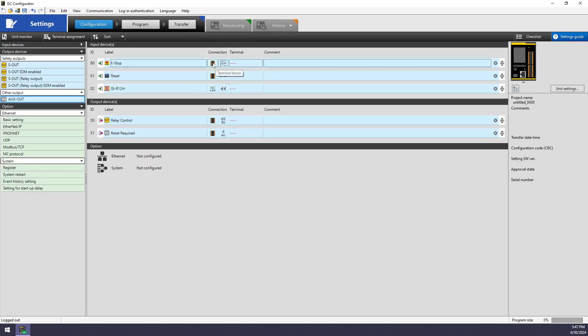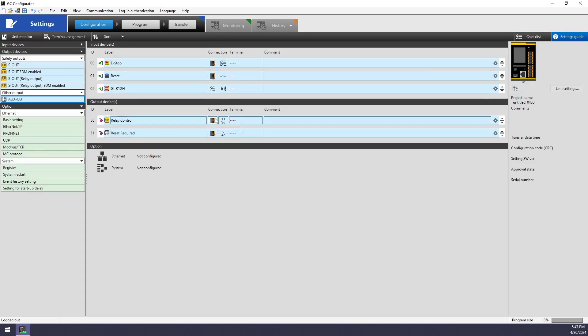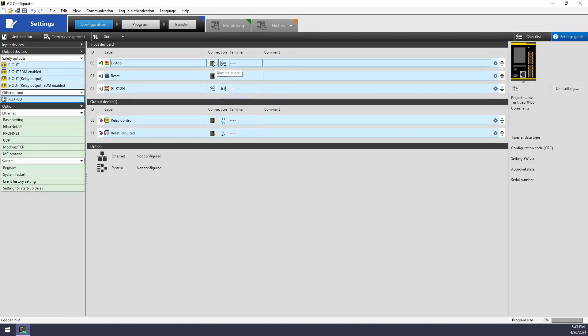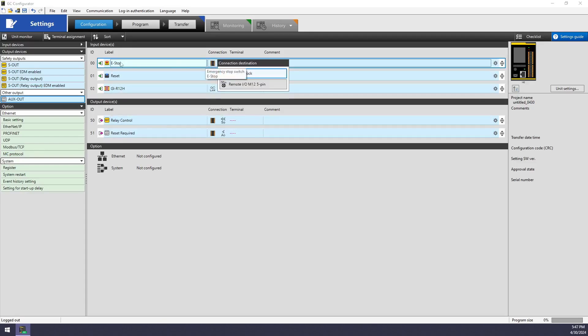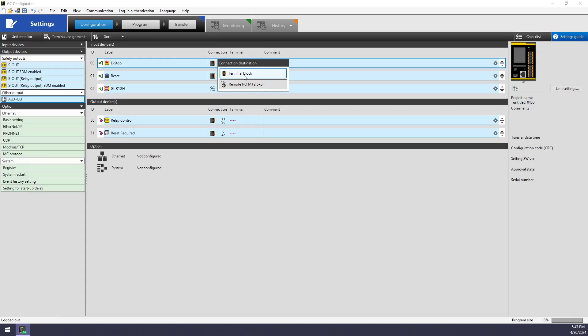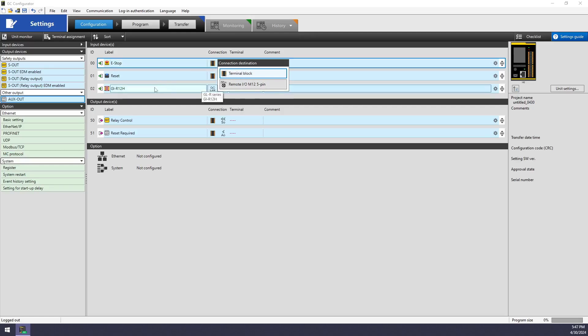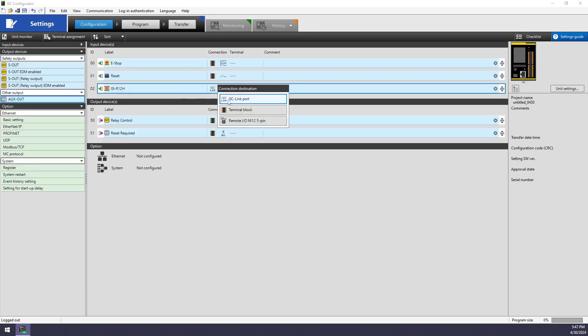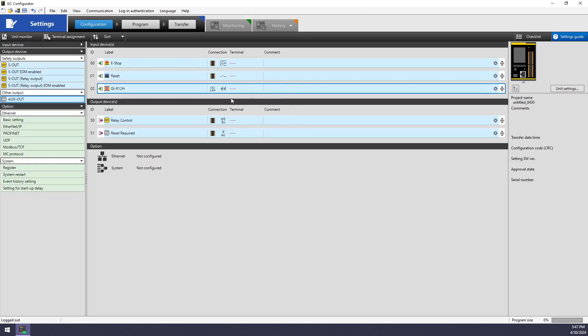Next, you need to tell the GC how every input or output device is going to be connected. So if you click on any of these icons, you will see the options for that type of input device. For my e-stop, I can have it connected either to the terminal block on the front of a GC unit, or to a remote I.O. module, that M12 5-pin quick disconnect. I'm going to keep everything with the terminal block except for my light curtains, which I will be using the GC link port connection. That's the quick disconnect cables, so no wiring involved with that type of connection.